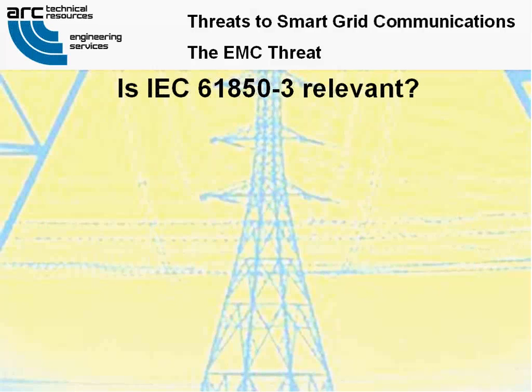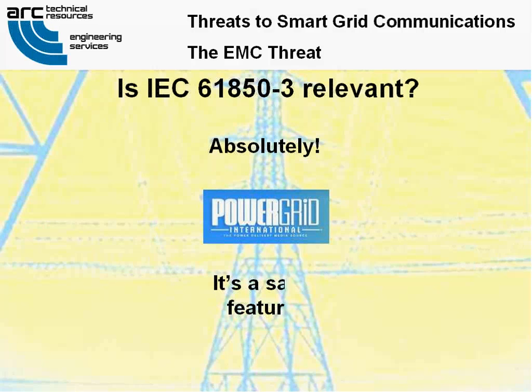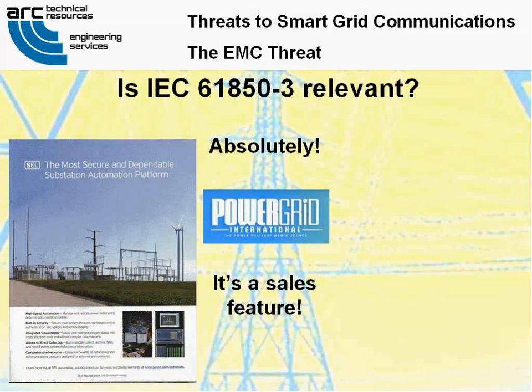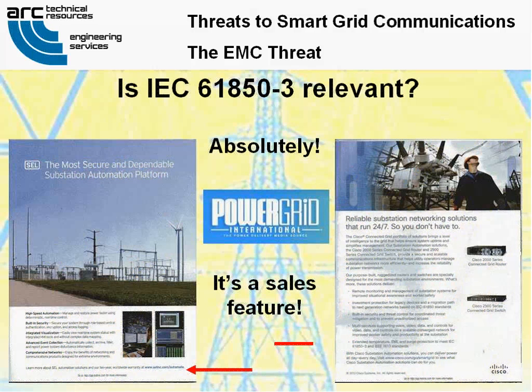Is IEC 61850-3 relevant to our work? Absolutely. Recent advertisements in Power Grid International magazine would indicate it's a sales feature. The link from the SEL ad touts that their communications products are, quote, hardened to meet stringent IEEE and IEC tests for harsh environments, unquote. The Cisco ad on the right notes that our ruggedized routers and switches already comply with IEC 61850-3 and IEEE 1613 standards. It also notes that, quote, next generation networks, unquote, will be based on IEC 61850-3 standards as investment protection.